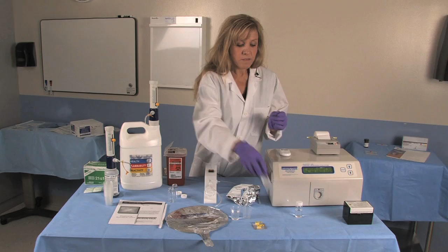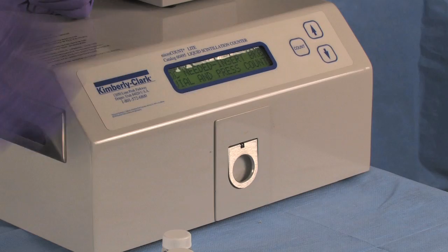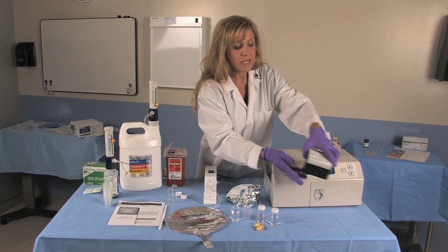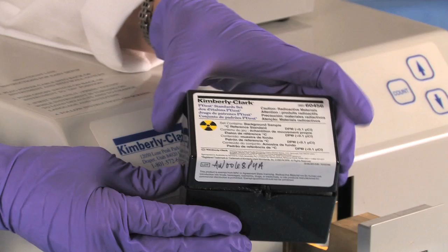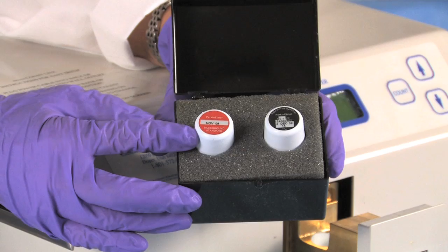Now I want to talk to you about the microCOUNT LITE. This is a liquid scintillation counter. It employs a couple of photomultiplier tubes to count the disintegration events that occur within the vial. You will need a calibration standard set. In the standard set box are 2 vials. The red capped vial is the background standard.